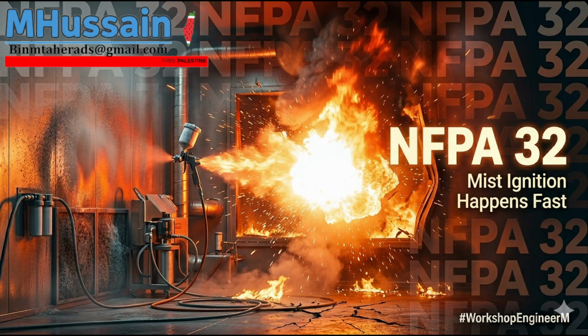So prior to 2016, the standard was still carrying all that heavy architectural baggage of the 1950s and 60s, right? Yes. The rules were written assuming you're using highly volatile chemicals in relatively open, unmonitored machines. Meaning, if an owner bought a state-of-the-art, hyper-safe, closed-loop machine using a high flashpoint solvent, the local fire marshal would still open the older NFPA code and force the engineer to build the facility to the safety constraints of a 1970s chemical plant. Which was incredibly frustrating for engineers.